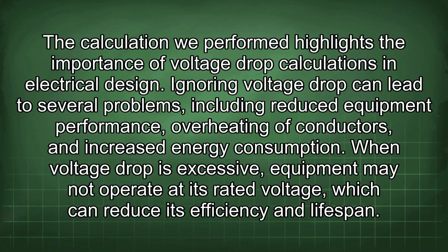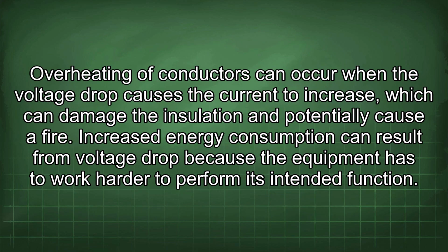The calculation we performed highlights the importance of voltage drop calculations in electrical design. Ignoring voltage drop can lead to several problems, including reduced equipment performance, overheating of conductors, and increased energy consumption. When voltage drop is excessive, equipment may not operate at its rated voltage, which can reduce its efficiency and lifespan. Overheating of conductors can occur when the voltage drop causes the current to increase, which can damage the insulation and potentially cause a fire.